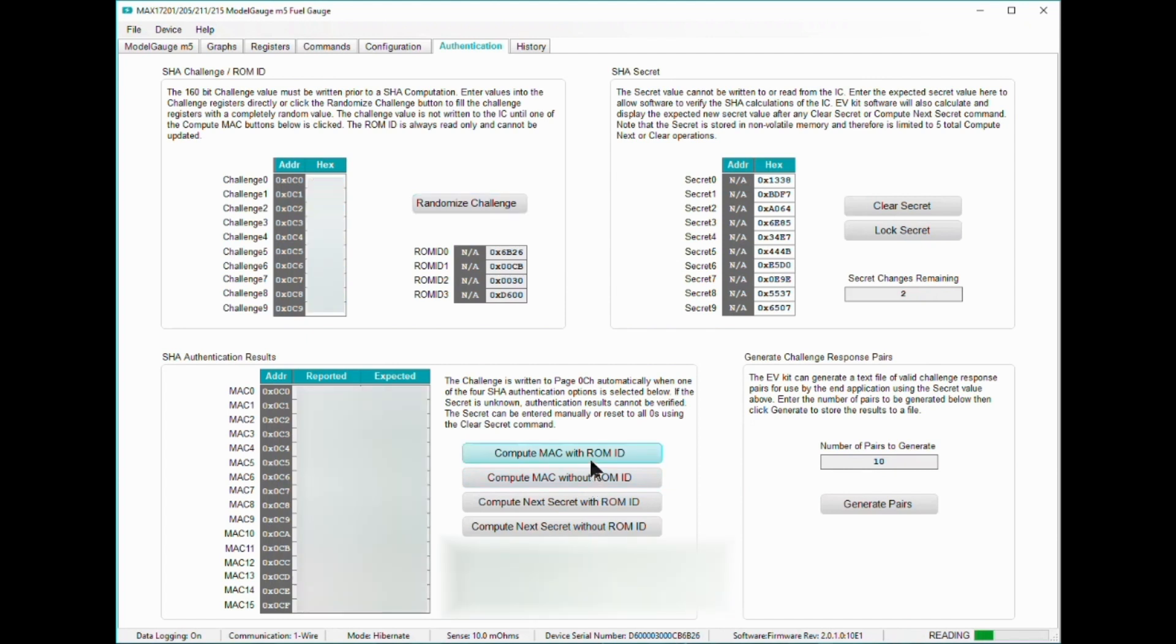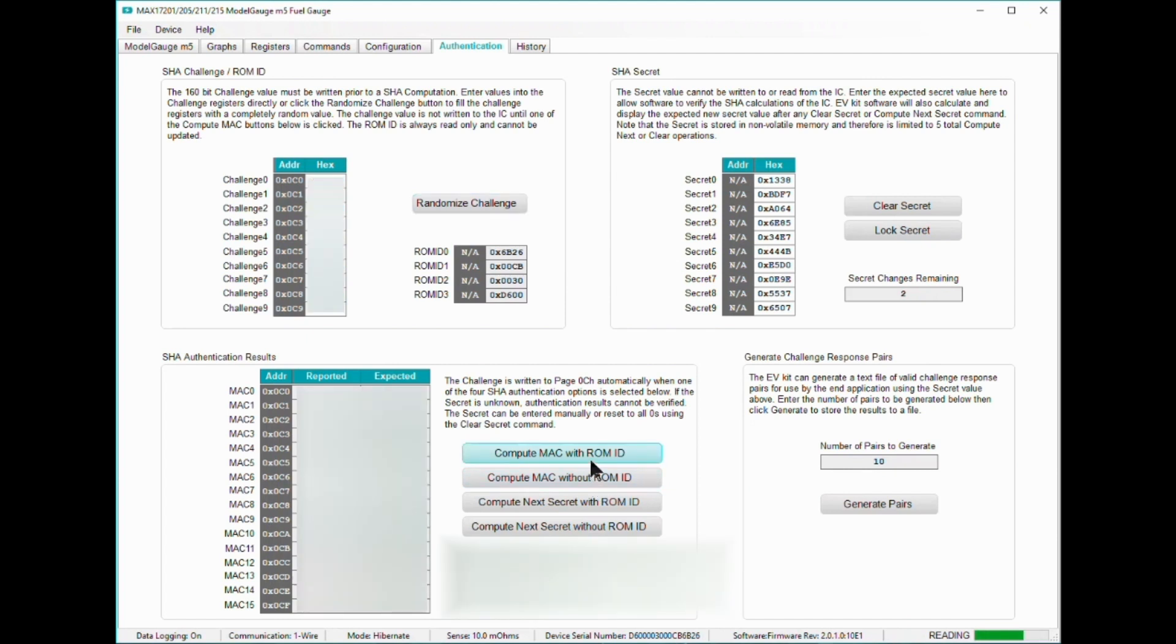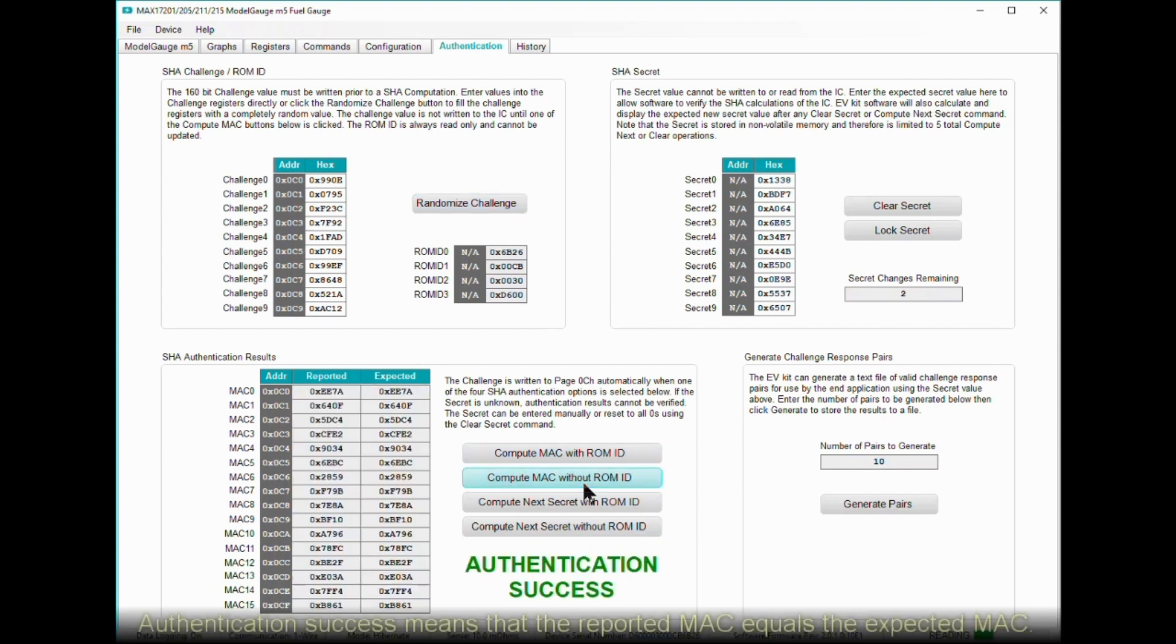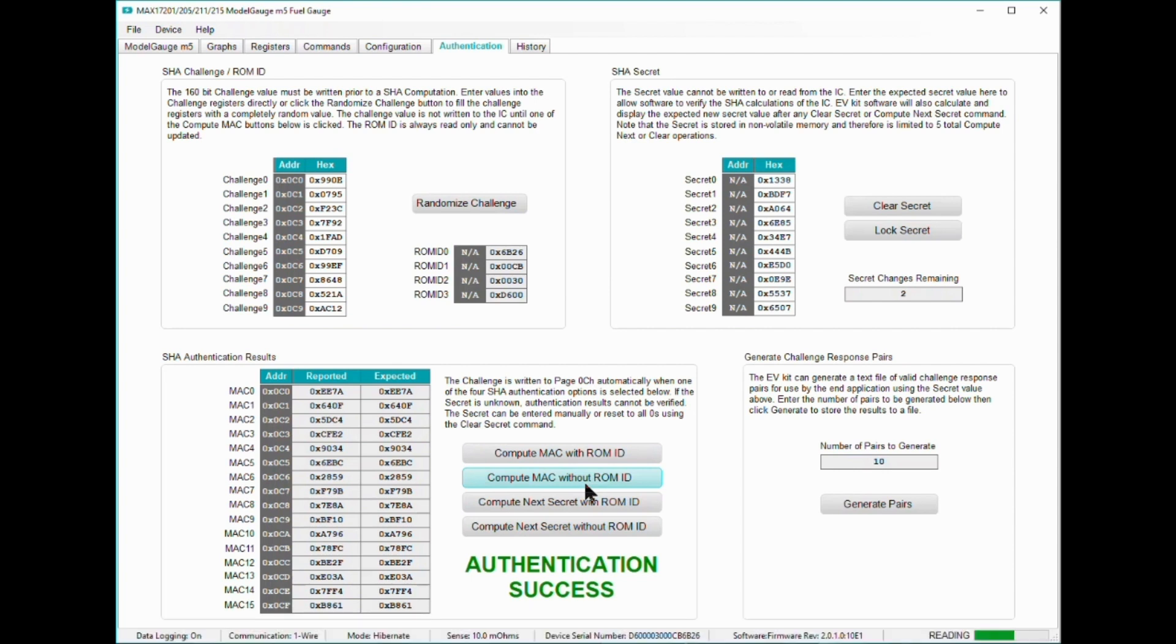To authenticate, use a random challenge and then click on the Compute MAC with ROM ID button. A success message should appear in the GUI saying that the MAC computed by the MAX17211 is the same as the MAC computed by the EVAL software. An identical MAC computation means that both the MAX17211 and the host, which in this case is the EVAL software, both know the same secret private key.